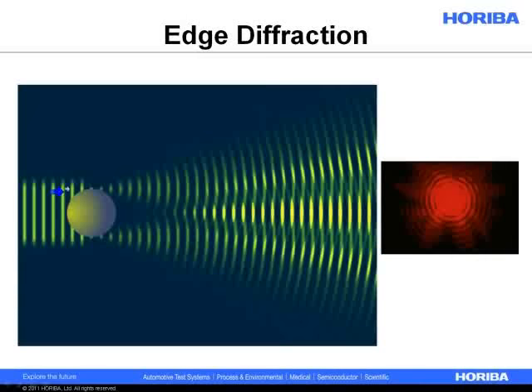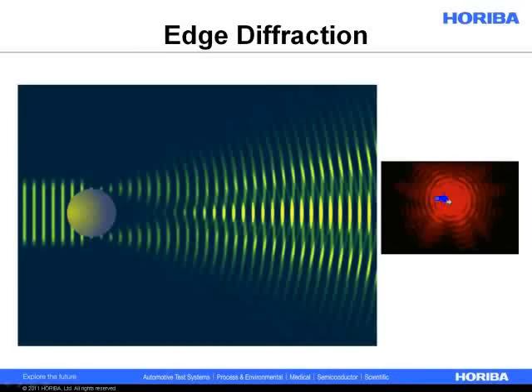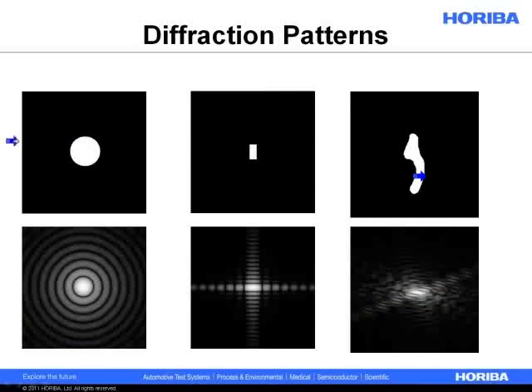Here's our basic mental model. We have a point scatterer in space with some well-behaved column of light hitting it. Typically in modern laser diffraction analyzers, this is laser light that hits the edge of the particle and begins creating interference patterns. It creates waves off of the two-point surfaces, and the waves begin to overlap. If you could rotate this image and look at it head-on, you would see radiating lines of minima and maxima. What we're really measuring with a laser diffraction analyzer is a diffraction pattern, also called a light scattering pattern or scattered light distribution.